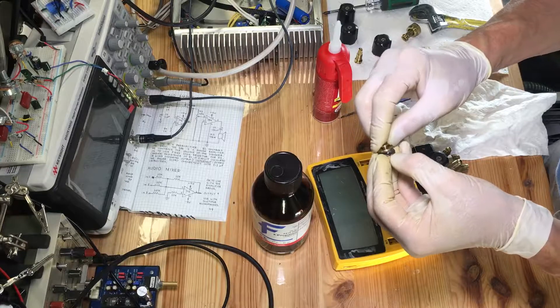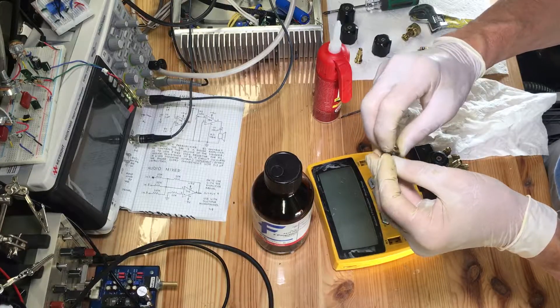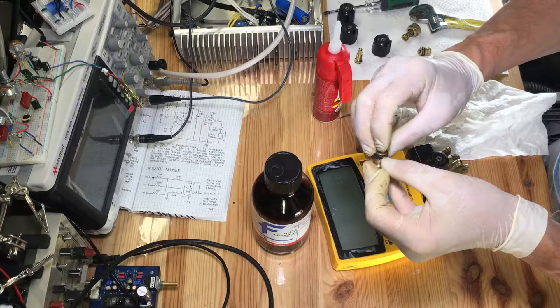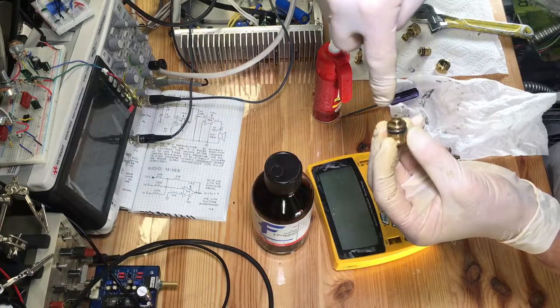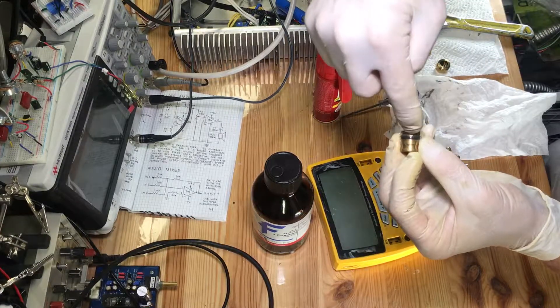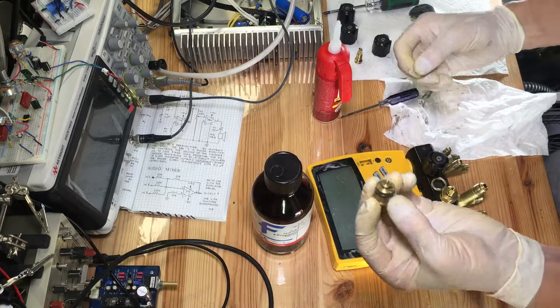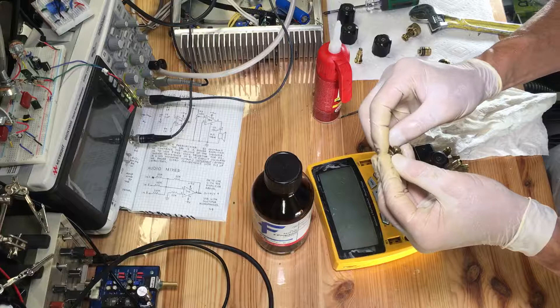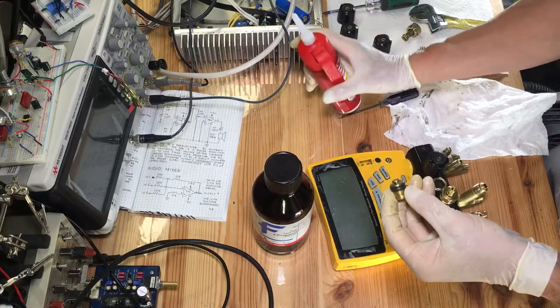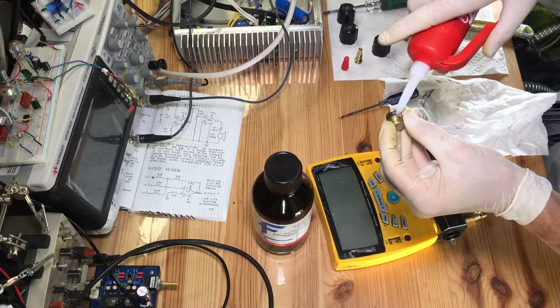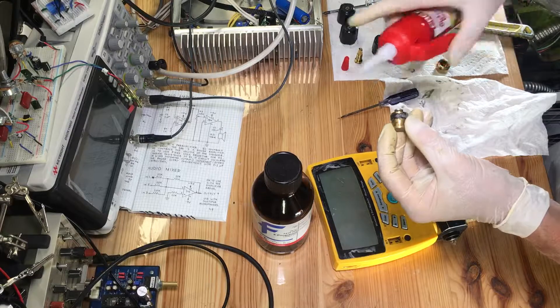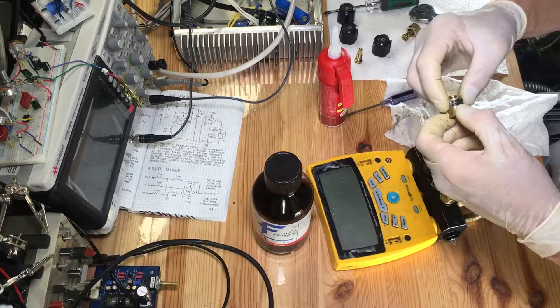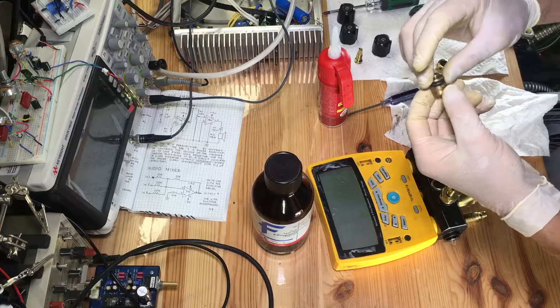Put it back into grooves, fill the grooves up, grab your o-rings. Now what this will do will make it so vacuum air cannot come down the stem and bypass through the backside of your o-rings, and you'll also have this on the front side too. Put it there, put it there. Okay, that's finished.